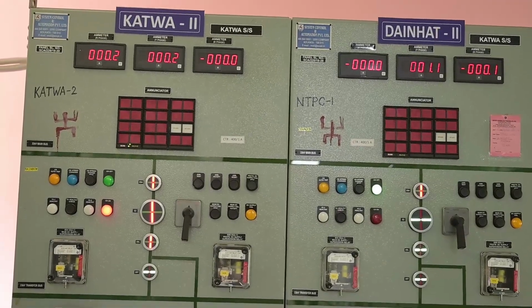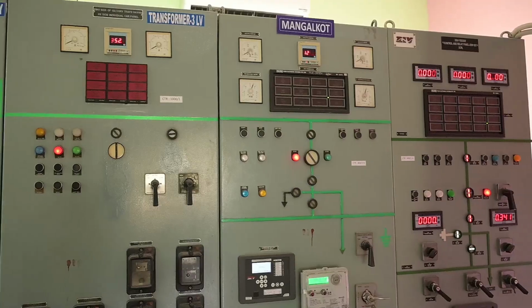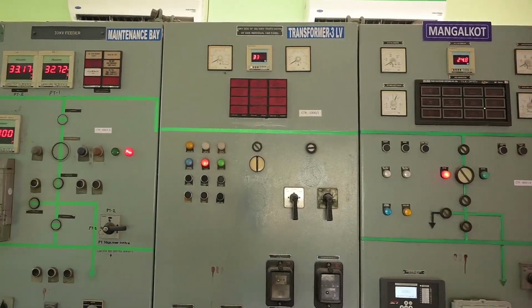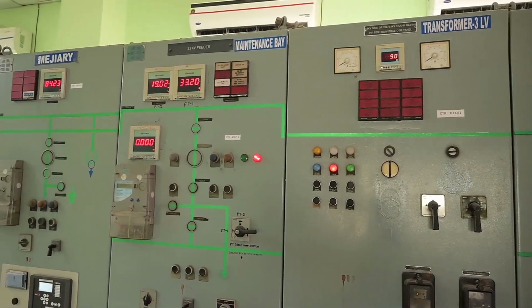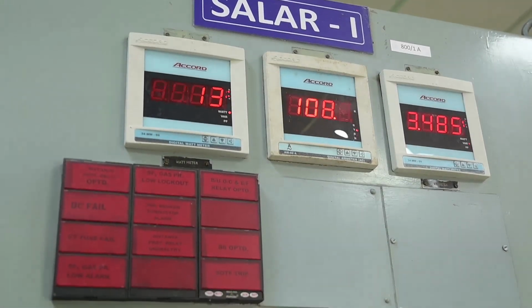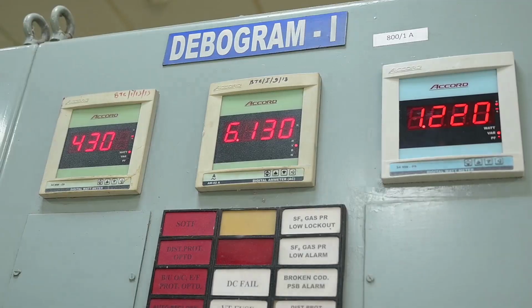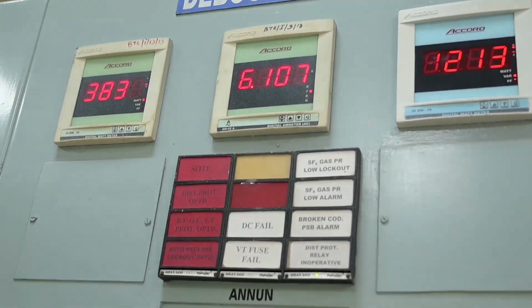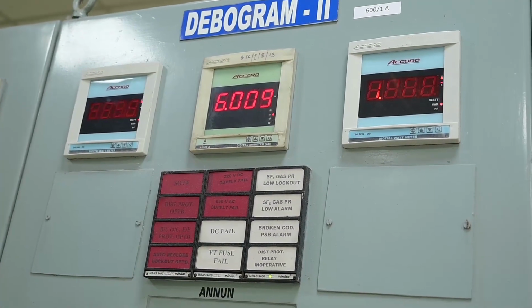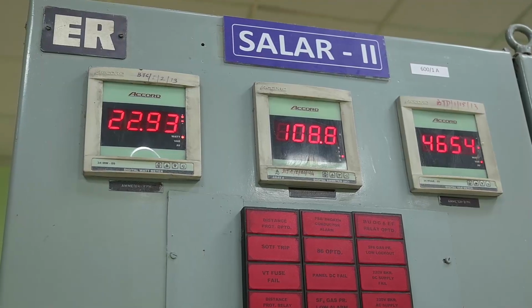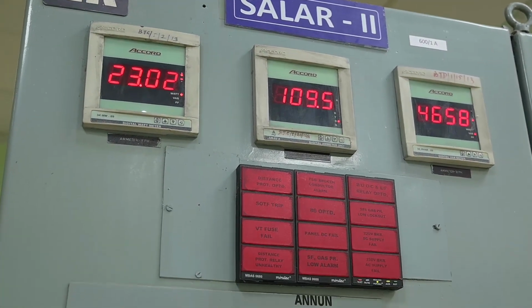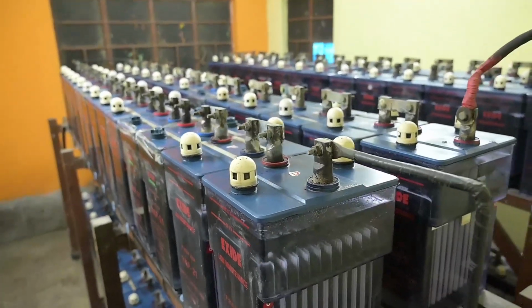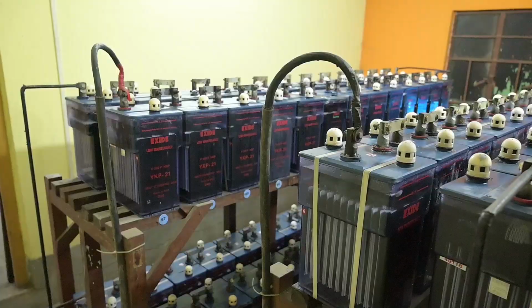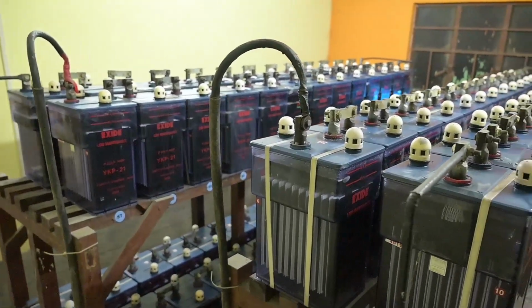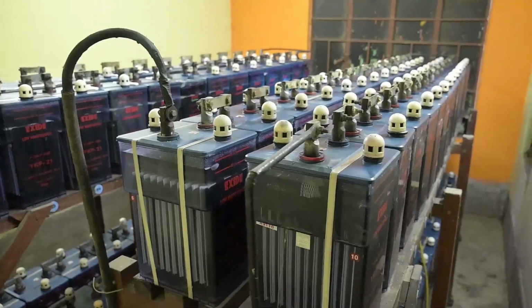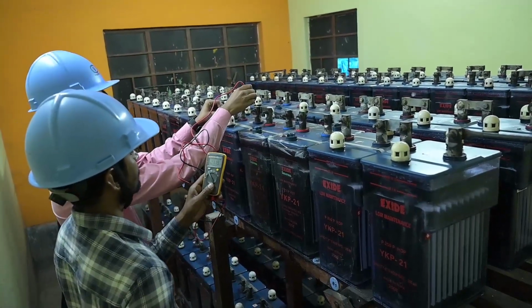Considering the importance of the 33 kV system, 7 numbers of age-old 33 kV panels were renovated recently. The 132 kV panels will be renovated shortly as part of ongoing efforts by WBSEDCL for increasing the redundancy and robustness of the control system. A second set of battery charger and battery bank has been incorporated at Katwa 132 kV substation. The battery bank and battery chargers are well maintained by the staff.